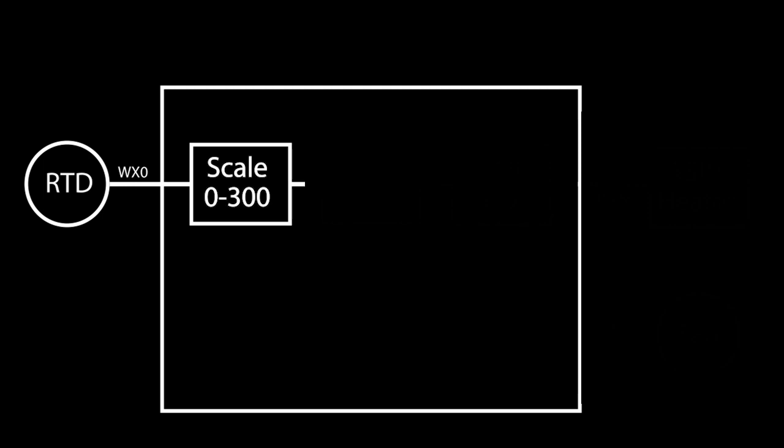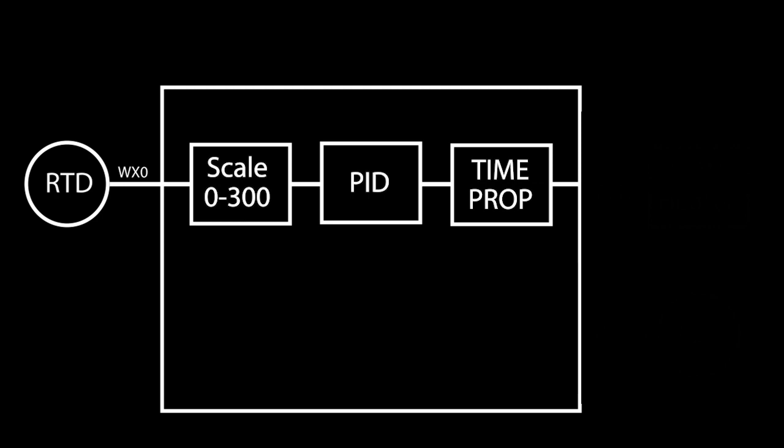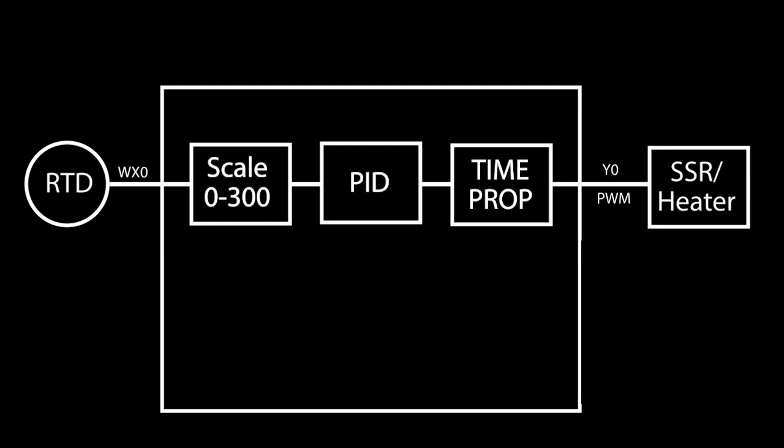Well great! We now have our raw temperature data which is scaled to 0 to 300 degrees Fahrenheit for us in the analog input setup. The PID instruction takes that, does its math and then passes a 0 to 100 percent to the time prop instruction which creates the PWM signal to control the solid state relay and ultimately the average heater power. And we also enabled the exhaust fan.